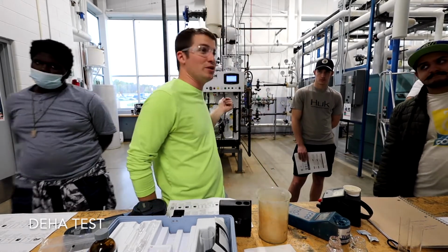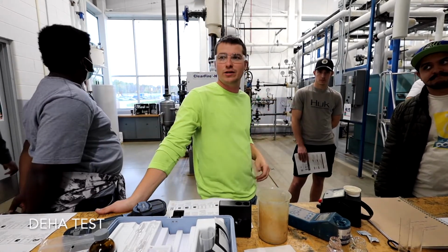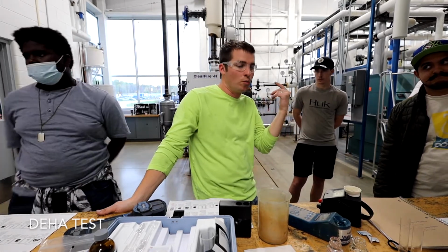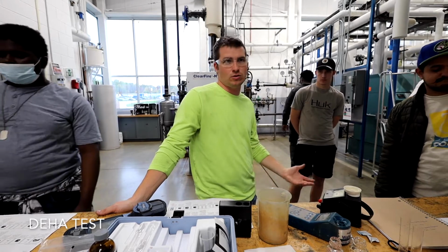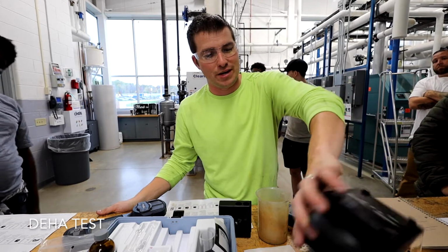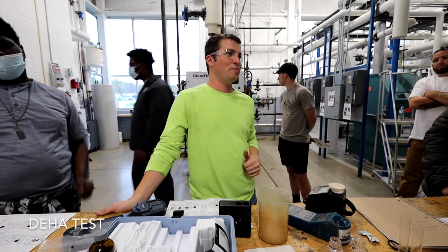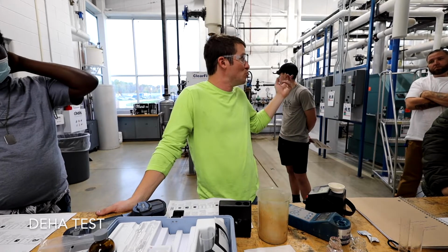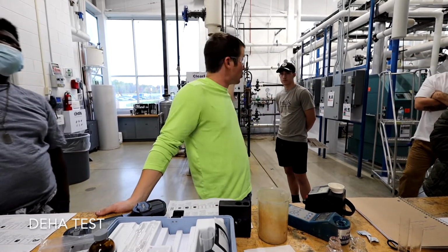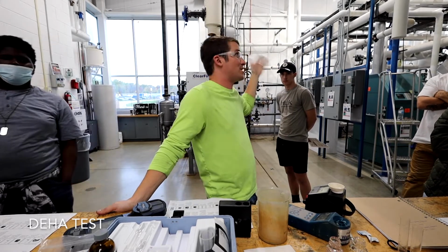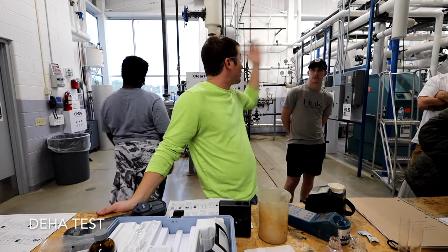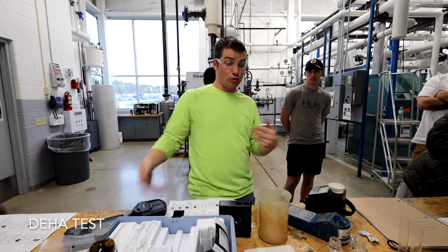It kicked on for 3 seconds so far for the hour we've been in here or whatever. We're never going to feed enough chemical the normal way when that's how it runs. It should run a better way, but there's not really a better way to make it run, unfortunately. The only way to make that run better is to run the boiler. But you can't, because you don't have any demand, right? There's no demand. You're calling for 2 pounds of pressure, and basically the system stays at 2 pounds of pressure all the time because it goes nowhere, right? It goes here.